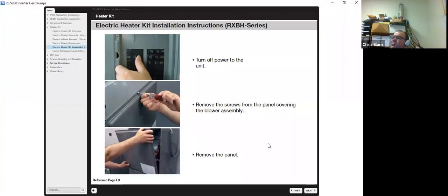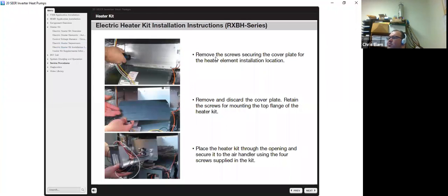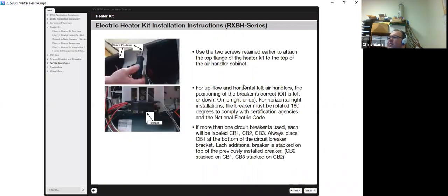This kind of explains the electric heat installation instructions. Most people do this before they wire it up. Turn the power off to the unit, remove the screws from the panel covering, remove the panel. In the back here, you will have screws. Remove the screws securing the cover plate for the element installation. Remove that plate, discard it, retain the screws, for the top flange of the heater kit. Gently slide the heater kit through the opening, and secure it into the pre-drilled screw holes. Using the top screws retained earlier, attach the top flange of the heater kit to the cabinet.